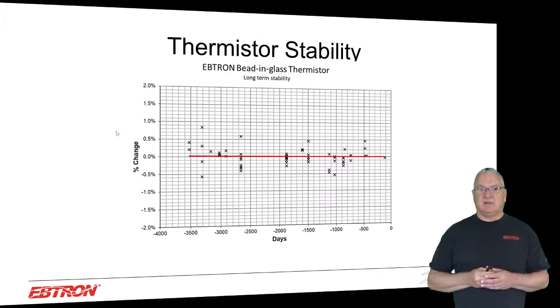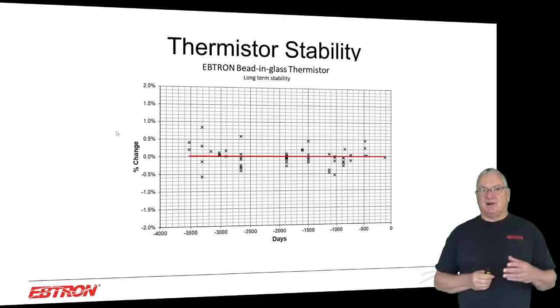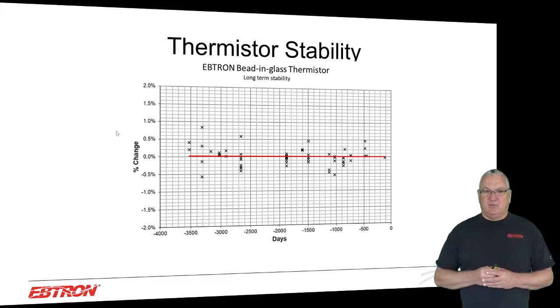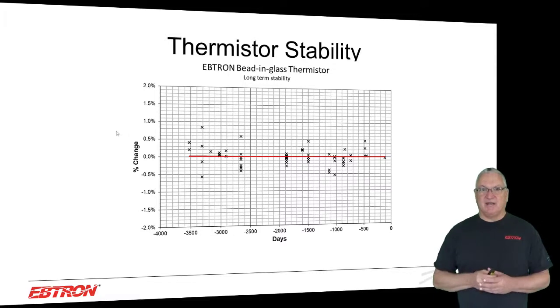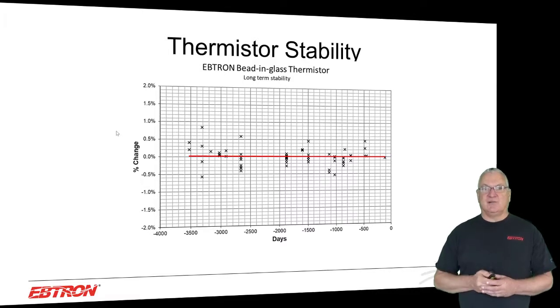When you look at thermistor stability, it's a big deal. We were fortunate enough to have our service department put some probes in the closet, and one day we dug them out, and we ended up having 10 years worth of parts in there, and we were able to take them apart and put them back into these baths and see what the resistance temperature characteristics were of these older products. And when we plotted it, what we found was the best fit line is that red line. So over a 10-year period, we had no significant change in electrical resistance versus temperature, which is the key to making a thermal airflow meter and why it's key to use the bead-in-glass thermistor part. You're not going to get that kind of performance out of chip thermistors. So you have drift-free performance.